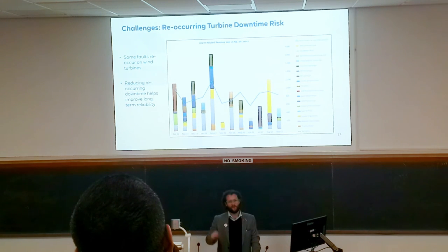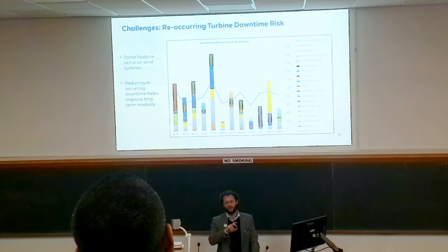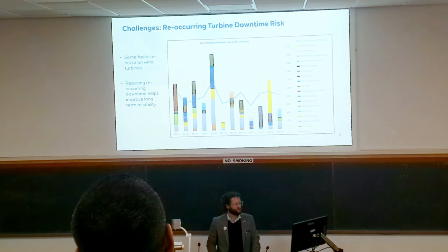Another challenge we have is managing reoccurring turbine downtime risk. You might think you fit a wind turbine and it operates perfectly with no problems, but that's absolutely not the case. What we have quite often is a number of small faults, like a fault with the cooling system or a fault with the fire detection system, and these can recur on every single turbine because they're all made by the same manufacturer. If you add those up over the year, they start to mount up into quite large numbers of losses.